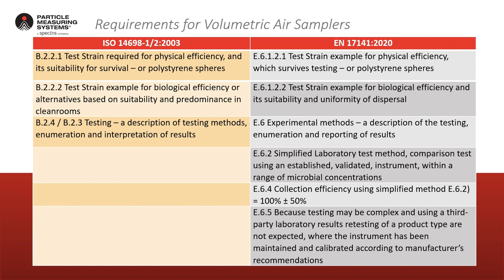Comparing ISO 14698 versus EN 17141 again: the test strain requirements and test methods are defined for both. E6-2 in 17141 talks about a simplified lab test method — a comparison against an established validated instrument. So if there's no provided information with your sampler for 17141, you can run a relatively rudimentary test. E6-4 specifies 100 percent plus or minus 50 percent. Results are performed in an open environment, sampling the flora and fauna in that area, which is a good reflection of what you're likely to see on a day-to-day basis.